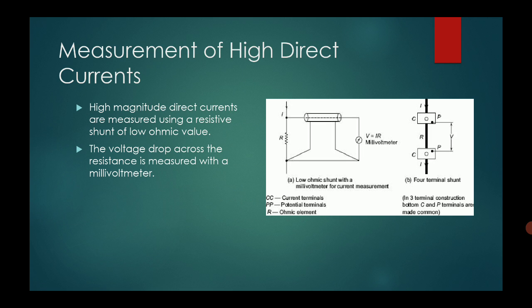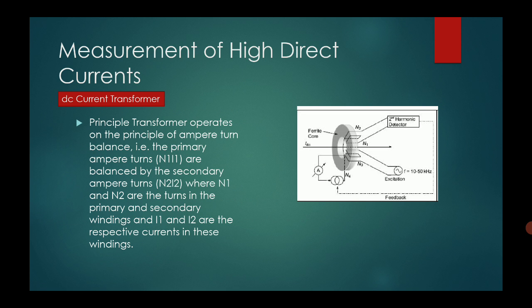For measurement of high direct currents, we have a setup with a low ohmic shunt and a millivolt meter. The current passes through this shunt, and it is the millivolt meter which actually measures the current. The high magnitude of direct currents are measured using a resistive shunt of low ohmic value. The voltage drop across the resistance is measured with the millivolt meter — from the voltage drop across a known resistance, we can calculate the current.